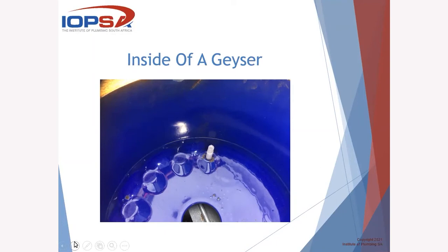So it'll start looking for those little pit marks, and it'll eat a little hole, and that's when your geyser pops and you get a little hole. With the pressure of the water in the geyser, it squirts through there, and you get a phone call to say, please come replace my geyser, it's burst.